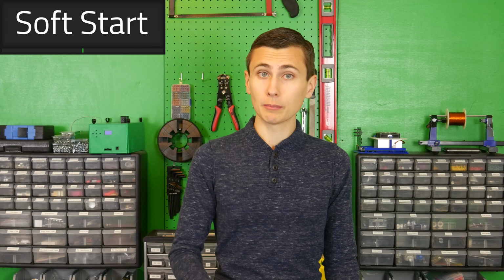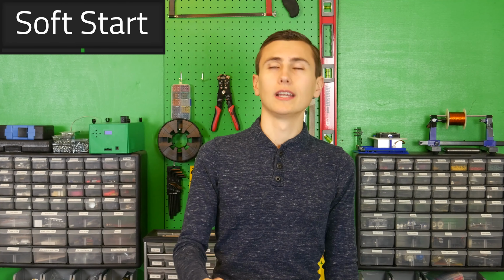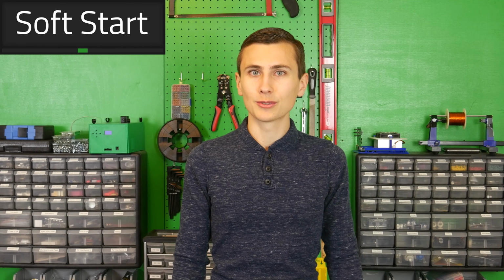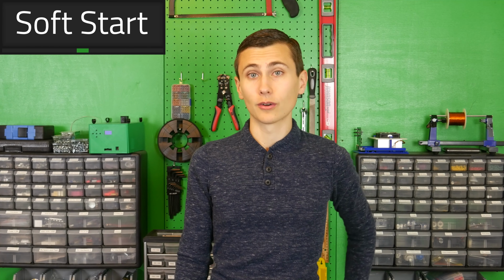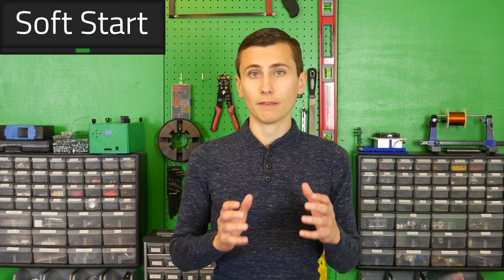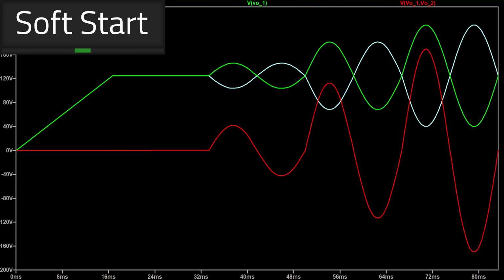This brings us back to that soft start routine. The routine that we implemented has 2 phases. Well, technically 3, but the third phase is just being on, so the first 2 are the most interesting. When transitioning from off to on, there are 2 things that need to happen. First, we need to bring the common mode DC voltage on both inverter outputs up to 1/2 the maximum DC voltage. Once that common mode base has been established, we can then ramp up the amplitude of our sine wave.